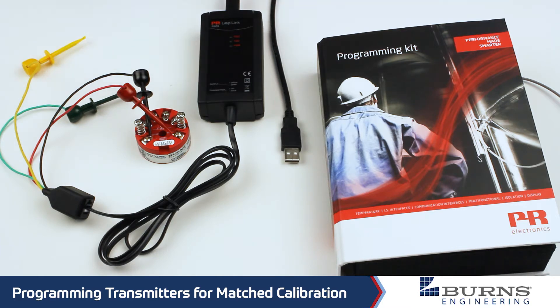The transmitter by itself is about a tenth of a degree C, depending on the temperature range it's set to. The PRT itself, if we get an uncalibrated version with just a class A interchangeability, it's plus or minus 0.13 degrees C at zero. But as you go away from zero degrees, that number gets quite large — at 100 degrees it can be up to nearly half a degree C. By doing a matched calibration, we eliminate the interchangeability of the PRT, so that half-degree number pretty much goes away except for the calibration uncertainty of the lab. Our lab is plus or minus 0.025 degrees C, so quite a huge difference.